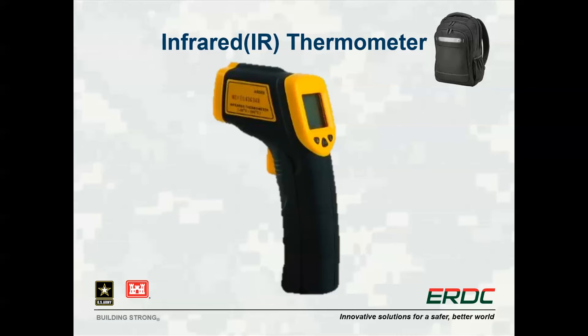The infrared thermometer is used to measure surface temperature, and is particularly useful for determining hot and chilled water line temperatures where other sensors are not available. This can help you quickly understand flow in a simple or complicated water or air system. Surface temperature readings near certain lighting fixtures can also help identify lamp type without physically removing the lamp. For example, recessed can lighting with incandescent bulbs and LED bulbs can look the same from 20 feet away, but incandescent bulbs may read 30 to 40 degrees Fahrenheit over ambient temperature, whereas LED bulbs are unlikely to be more than 10 degrees Fahrenheit over ambient for an open fixture.